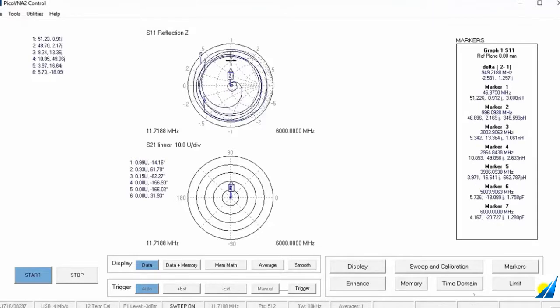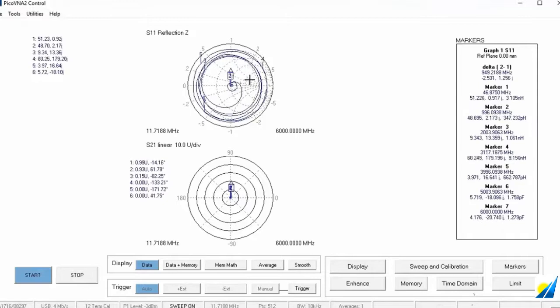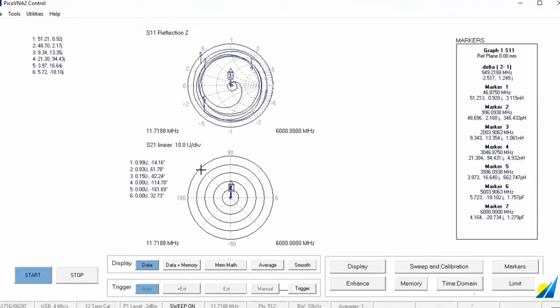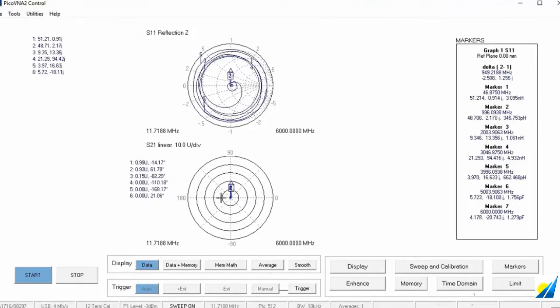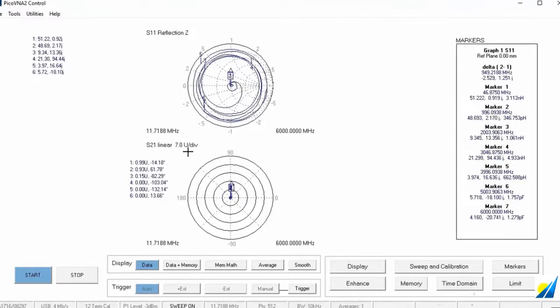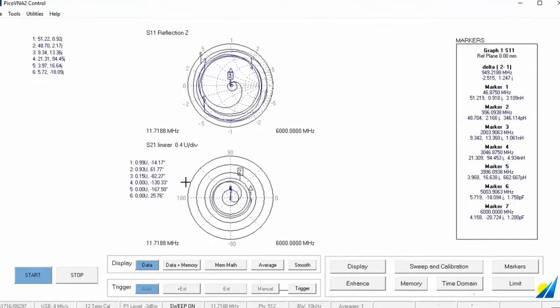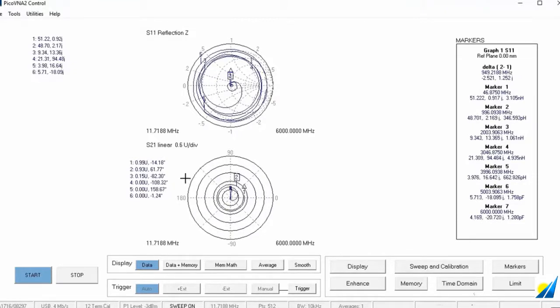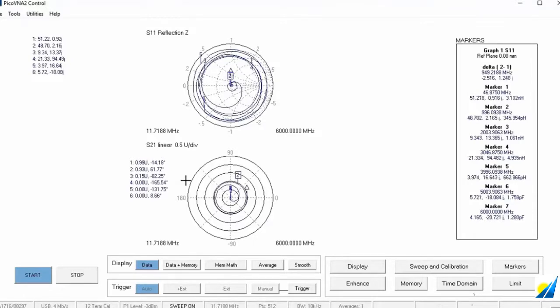Even on these polar plots, we are able to grab hold of markers and pull them around and look at any feature we wish to on the polar plot. The polar plot at the bottom of the display, that's not looking very sensible at the moment. It looks like all of the data is in the middle of the screen, in the middle of the plot. Let's pull up the sensitivity there. We can see we pull that out to, there we go. We can see the detail more simply by pulling out the sensitivity of the readout or of the plot.